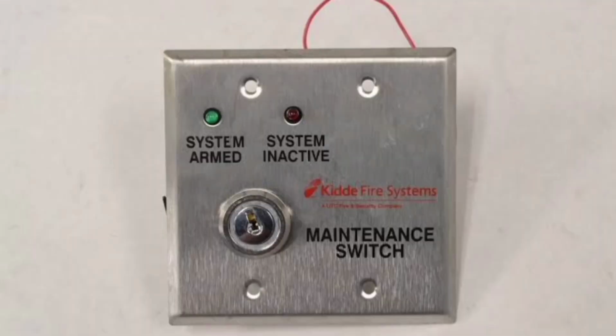It physically disconnects the circuit wiring, causing a trouble signal, and provides the means to generate a supervisory condition in your fire alarm control panel. The crucial thing is that the key can only be removed in the system armed position.